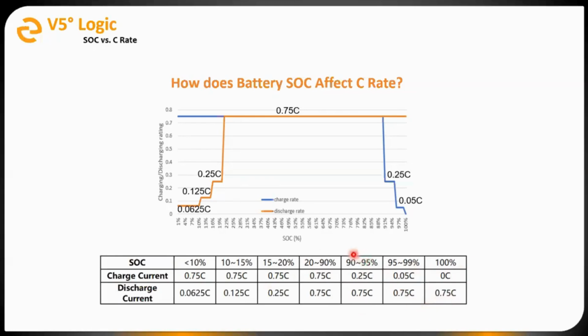One thing I want to point out specifically related to charge current, once we get into this higher SOC range: notice all up until we get to 90% state of charge, the battery is going to let you charge it at its full rated current. Once we hit 90%, however, it limits the charge current to just 25 amps. So between 90 to 95%, we're only charging at 25 amps. And then between 95 to 99%, the charge current bumps down all the way to just 5 amps.